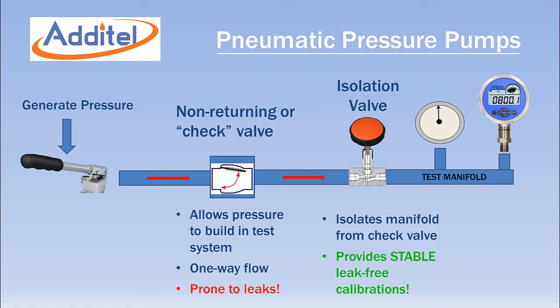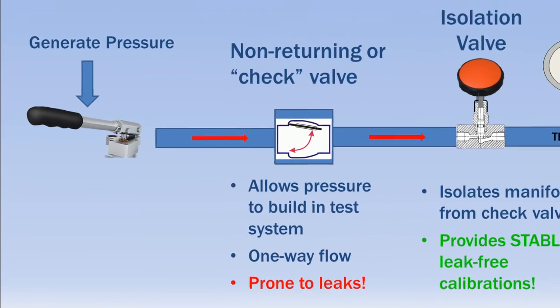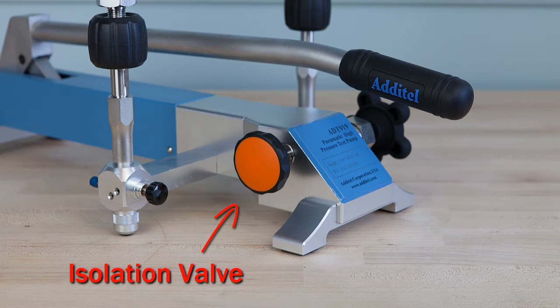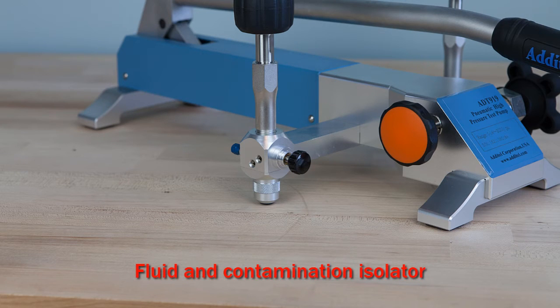Most pneumatic pumps in the market have non-returning or check valves that allow pressure to be built up in the test volume. These valves are often prone to leakage as seals wear. Additel pumps include a valve that isolates the calibration volume from the check valve, providing stable calibrations even as seals degrade over time.